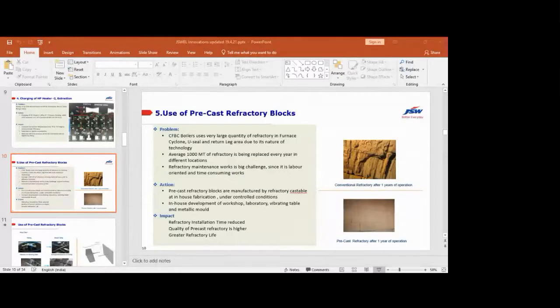So, sir, use of precast refractory blocks. As we know, in a CFBC boiler the erosion is higher than in other boilers. So we have a high erosion rate, and to protect the water wall tubes or plates, we provide refractory. This refractory is in large quantity in the furnace, cyclone, U-seal, and return leg area. On average, 1,000 metric tons of refractory is replaced every year in different locations. Refractory maintenance work is a big challenge since it is labor-oriented as well as time-consuming.